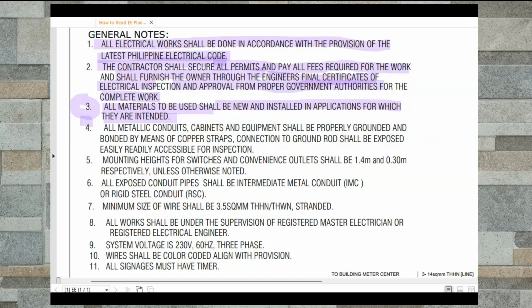Number 4: all metallic conduit, cabinets and equipment shall be properly grounded and bonded by means of copper straps. Connection to ground rod shall be exposed, easily and readily accessible for inspection. So all metallic conduit and cabinets should be properly grounded.